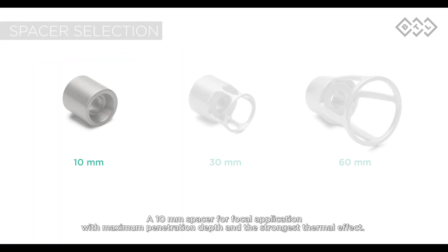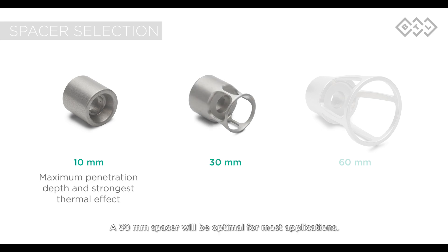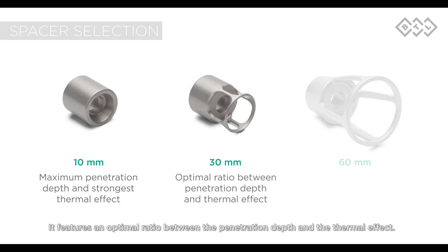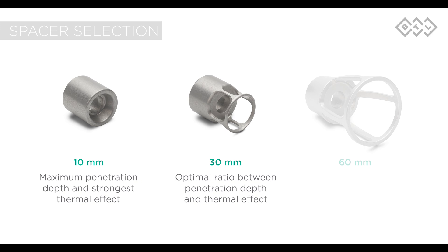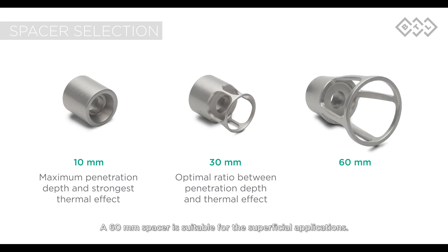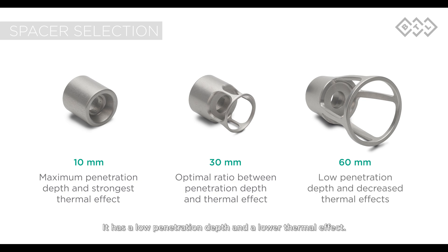There are three spacers available. A 10 mm spacer is for focal application with maximum penetration depth and the strongest thermal effect. A 30 mm spacer will be optimal for most applications, featuring an optimal ratio between penetration depth and thermal effect. A 60 mm spacer is suitable for superficial applications — it has a low penetration depth and a lower thermal effect, and is suitable for the treatment of acute and superficial conditions.